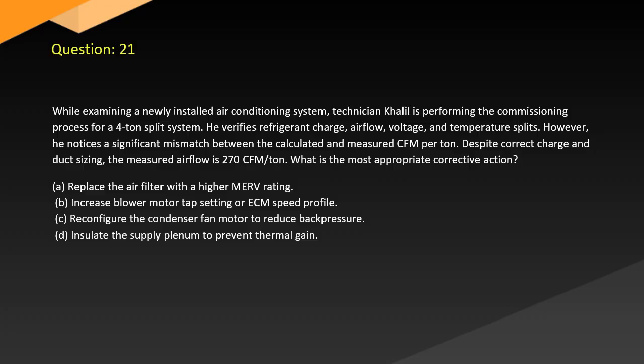Question 21. While examining a newly installed air conditioning system, technician Khalil is performing the commissioning process for a 4-ton split system. He verifies refrigerant charge, airflow, voltage, and temperature splits. However, he notices a significant mismatch between the calculated and measured CFM per ton. Despite correct charge and duct sizing, the measured airflow is 270 CFM per ton. What is the most appropriate corrective action? A. Replace the air filter with a higher MERV rating. B. Increase blower motor tap setting or ECM speed profile. C. Reconfigure the condenser fan motor to reduce back pressure. D. Insulate the supply plenum to prevent thermal gain.